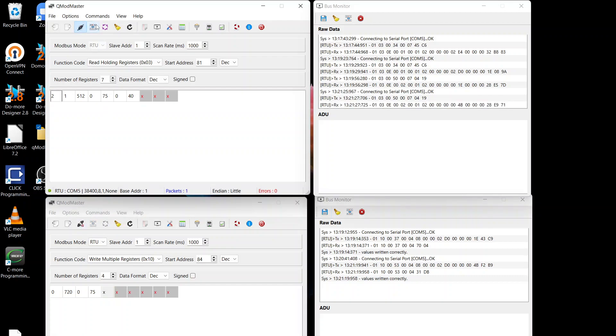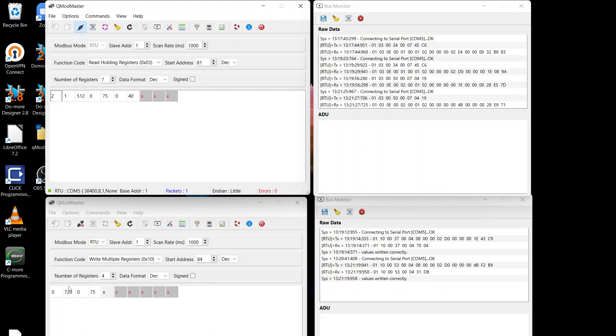When we read, you can see that the 0, 75 has been written into the incorrect holding register. And this 0, 720 has been lost. So 0, 75 has been moved over to registers, written in the correct location. And obviously those ones have been lost. Even though if you actually go through and have a look at the raw data that's been sent and you break it down, the correct values are being sent. But for some reason, the dose controller just seems to be putting it in the wrong spot.